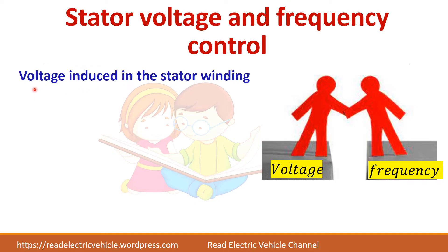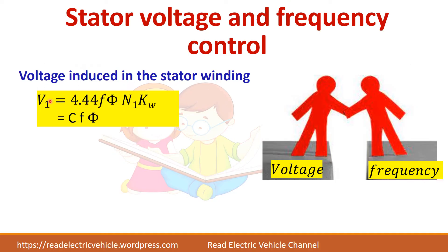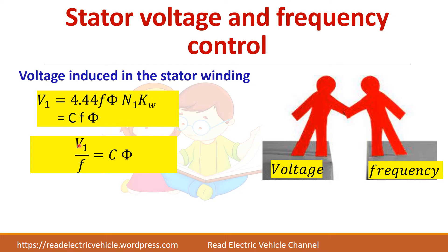The voltage induced in the stator winding is given by the equation where all terms are constant except F and φ. Taking C as the constant term: V1 = C × F × φ. Rearranging, V/F = C × φ. So if we keep this ratio V/F constant, flux will be constant, and if flux is constant, torque will be constant.